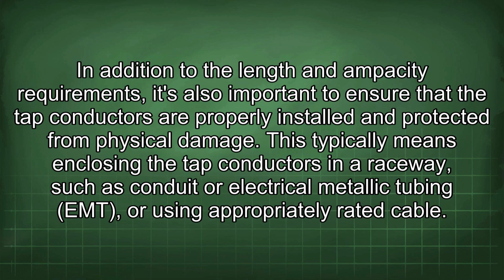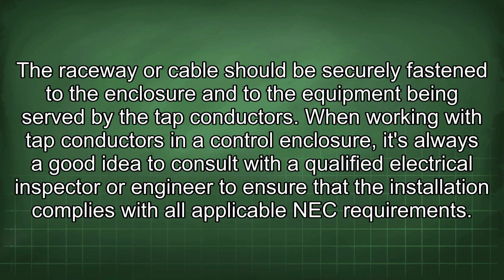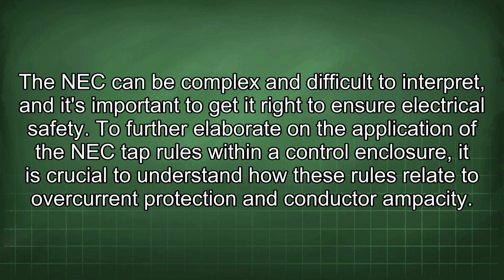In addition to the length and ampacity requirements, it's also important to ensure that the tap conductors are properly installed and protected from physical damage. This typically means enclosing the tap conductors in a raceway, such as conduit or electrical metallic tubing, or using appropriately rated cable. The raceway or cable should be securely fastened to the enclosure and to the equipment being served by the tap conductors. When working with tap conductors in a control enclosure, it's always a good idea to consult with a qualified electrical inspector or engineer to ensure that the installation complies with all applicable NEC requirements. The NEC can be complex and difficult to interpret, and it's important to get it right to ensure electrical safety.